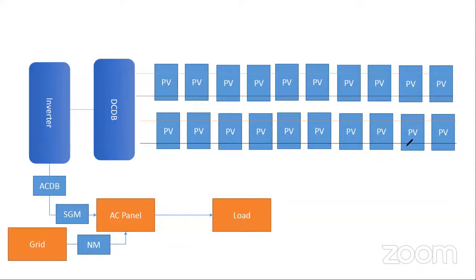So VOC is a standard, the open circuit voltage of a PV module as per the data sheet. If you connect 10 panels in series, then you need to cross-check that the 10 panels in series should not exceed the maximum string voltage that the inverter can accept as input. The maximum string voltage the inverter can accept is 600 volt. But as a factor of safety, if you consider 80% loading, it is 480 volt. Under the 480 volt, we are loading only 378 volt. So the system is safe. That is why we are cross-checking that.